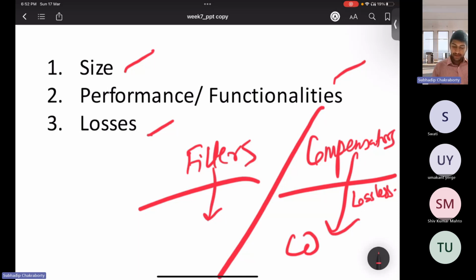If you are using passive compensators, they are designed to function at the power frequency to provide some reactive power compensation or power factor improvement, as well as load balancing, but only for this power frequency. For passives, they are fixed. For fixed loading, they can provide these functionalities.